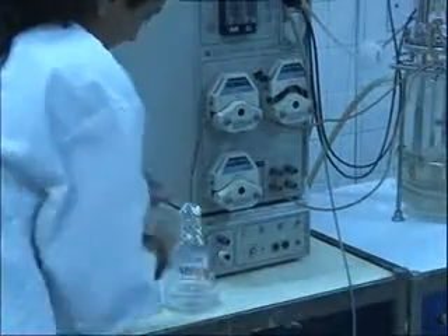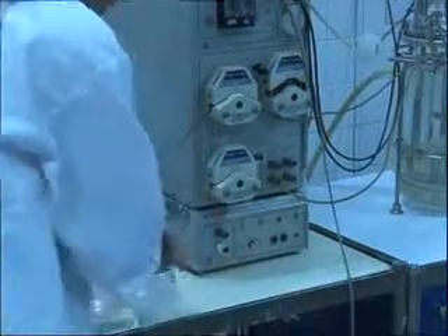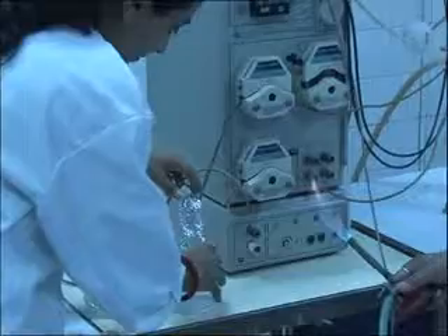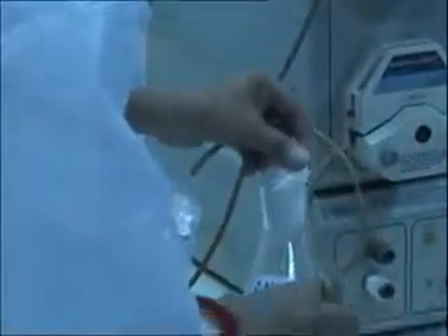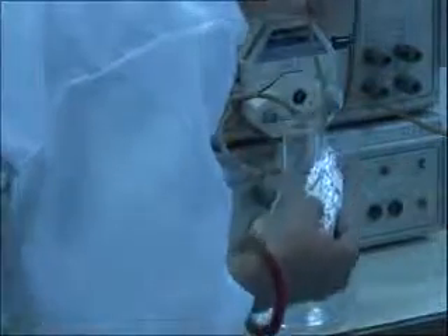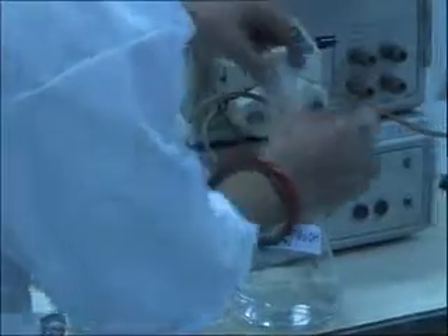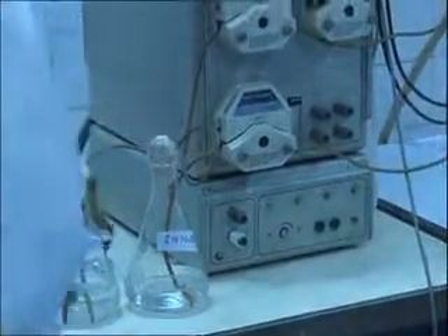Before we use them, we have to prime the pumps so that the liquid acid or alkali reaches the top of the vessel. Aseptically, we now connect the tubings to the acid and alkali bottles. So we bring the flame and the tube goes inside the flask as shown over here. Connect the plug of the acid bottle. Same way we do it for the base. Near the flame, we open the cap, put the tubing inside, and put the plug back into the flask. So the acid and alkali reservoirs are now connected to the controller.